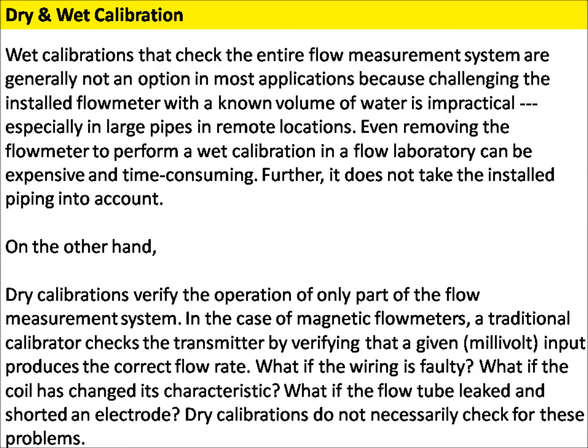On the other hand, dry calibrations verify the operation of only part of the flow measurement system. In the case of magnetic flow meters, a traditional calibrator checks the transmitter by verifying that a given millivolt input produces the correct flow rate. What if the wiring is faulty? What if the coil has changed its characteristic? What if the flow tube leaked and shorted an electrode? Dry calibrations do not necessarily check for these problems.